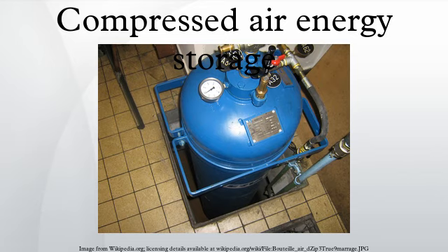There are a few categories of air storage vessels, based on the thermodynamic conditions of the storage and on the technology chosen: constant volume storage and constant pressure storage. Constant volume storage uses a chamber with rigid boundaries to store large amounts of air. This means, from a thermodynamic point of view, that this system is a constant volume and variable pressure system.